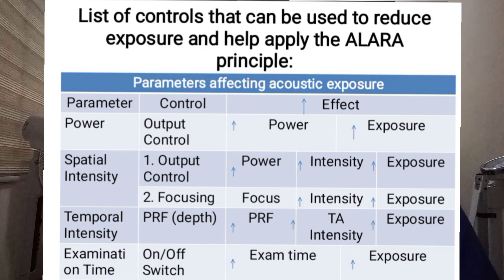So look at the parameters affecting acoustic pressure. The power, for example: the control will be the output control, and increased power will mean increased exposure, and that means increased effect. Spatial intensity: you can achieve that with the control button and focusing. Increased power, increased intensity means increased exposure. Increased focus means increased intensity, and that will be increased exposure. Then temporal intensity: the control is the depth and PRF. So increased PRF will mean increased TA intensity and increased exposure.